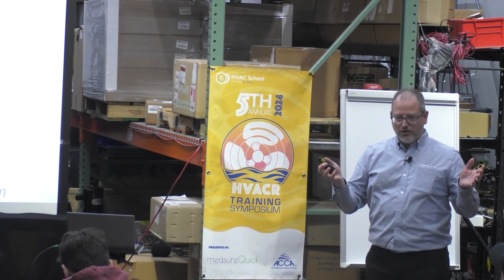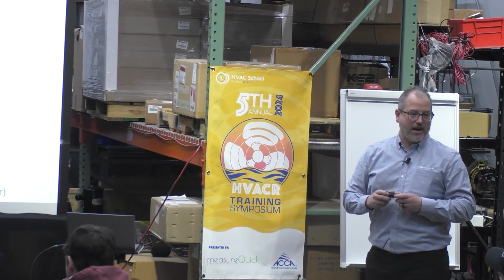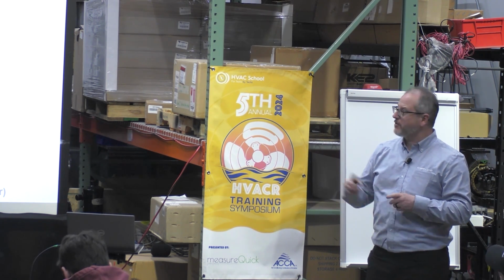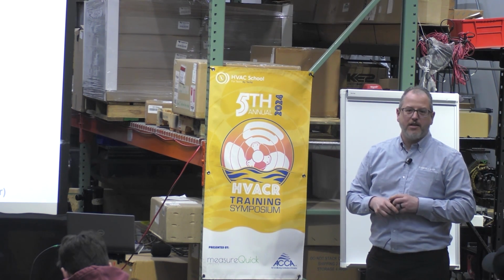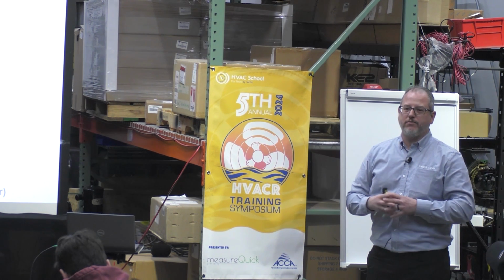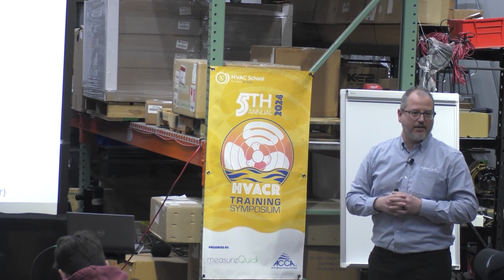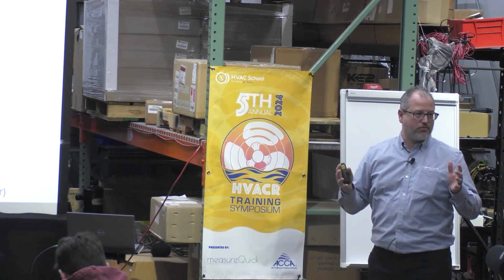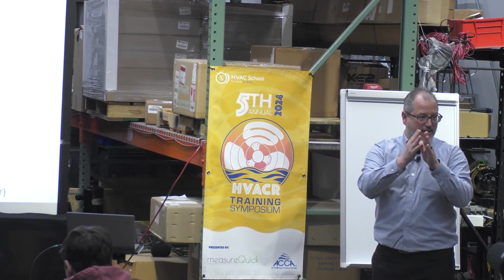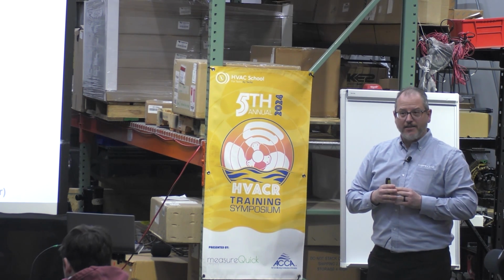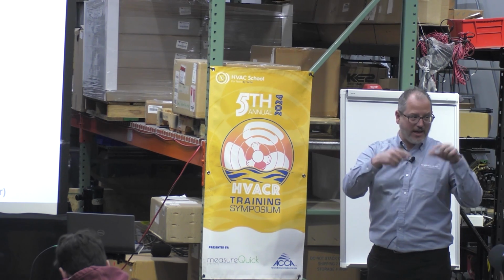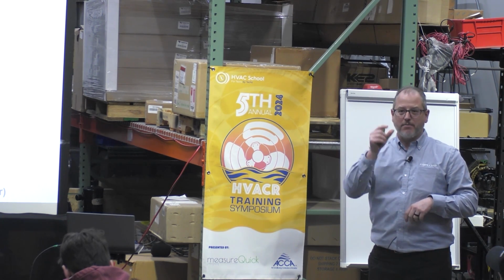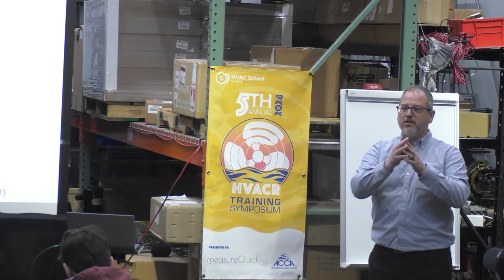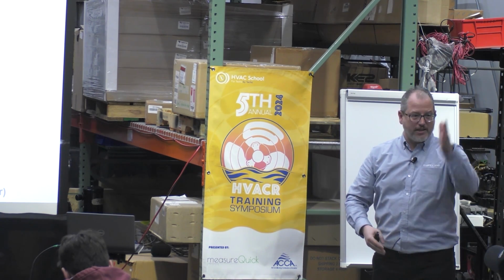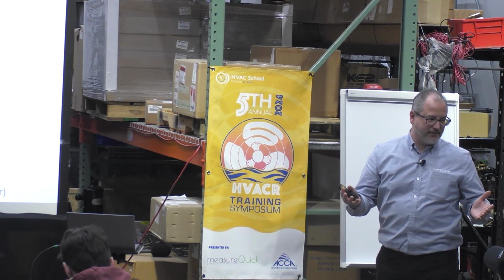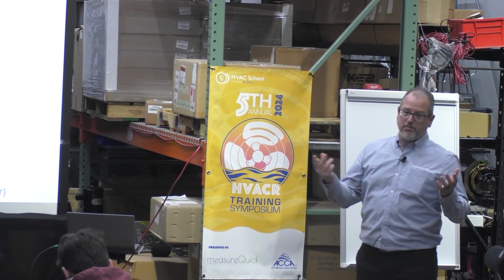I would say if you're the one that cleaned it and you know for sure. Because I personally have gone to units, I have some pictures that I put in some other trainings, where the person said, I cleaned every one of those units up on the roof, so the problem's not that. And I go up there, and this happened to be a very large rooftop, and it had a split condenser. So they cleaned it, but they did not split it, because I could see they obviously did not hit it, they had very old zip ties in the condenser holding it together. So you pull apart the condenser, and it looked like a blanket inside. That was not clean, right? Somebody said it was clean, but I didn't believe them.